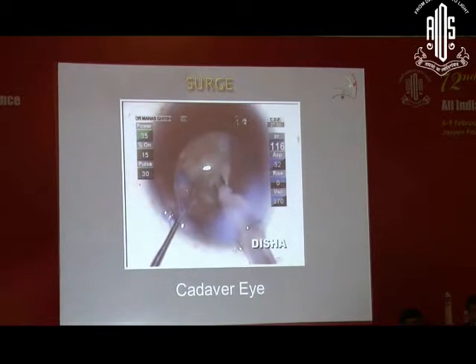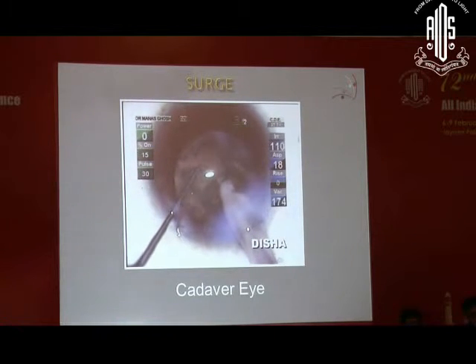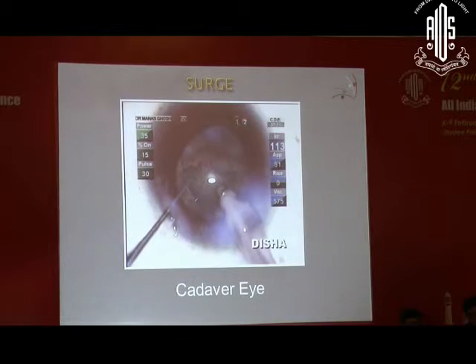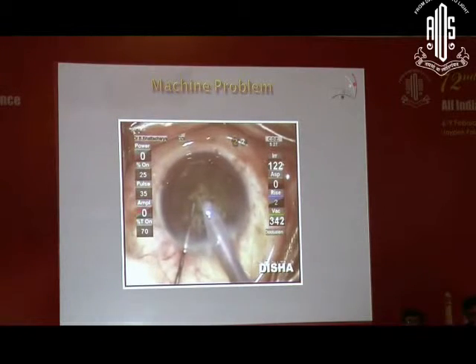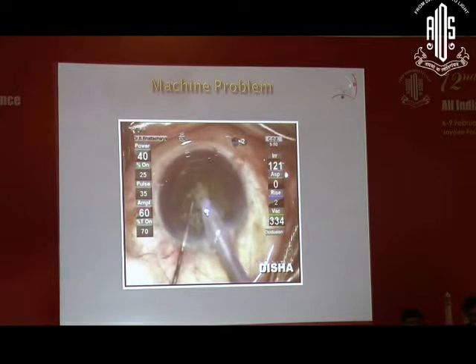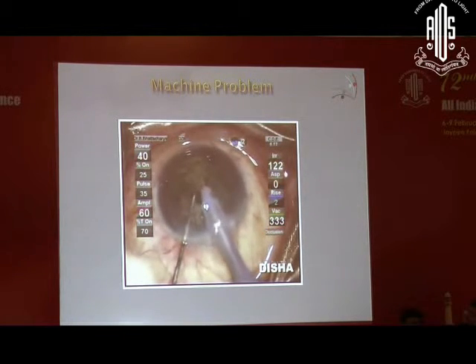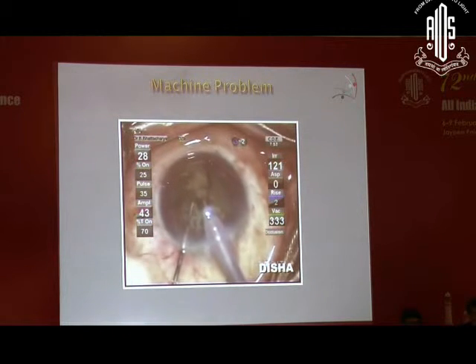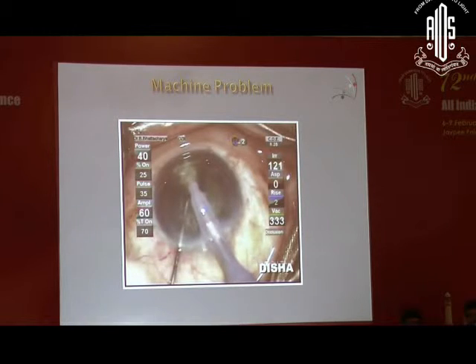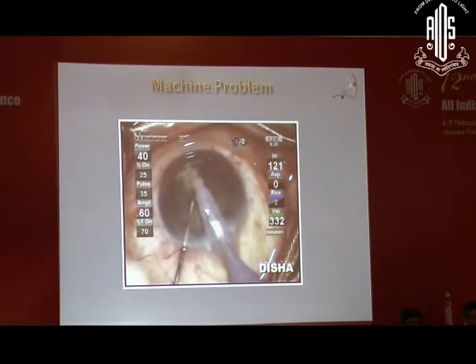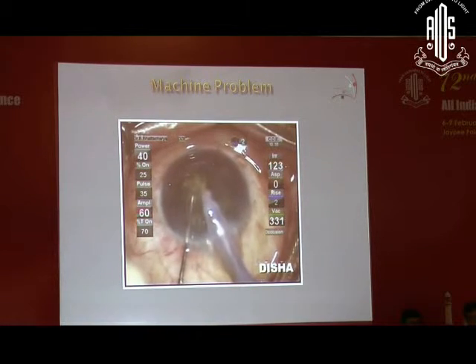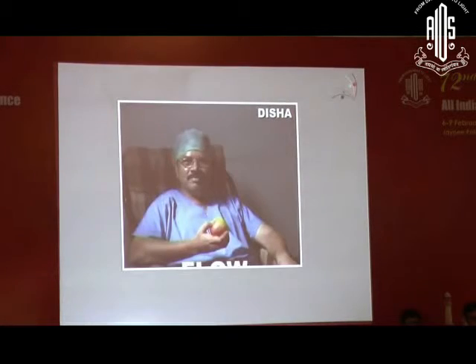Now surge, for obvious reasons, has been shown here. If you use too much vacuum, too much energy, what will happen? Things will happen very suddenly. The occlusion break will be sudden and the machine cannot take over, and that's how you have an incident here. So this gives you a feel of what things can go wrong and what is the right way of doing things. Sometimes around this, you see the vacuum is around 330, but nothing is happening, there is no hold. Actually the tubing or the tip has got occluded, so you need to prime the machine and change the tip. So these are machine problems which we have to solve on a day-to-day basis.